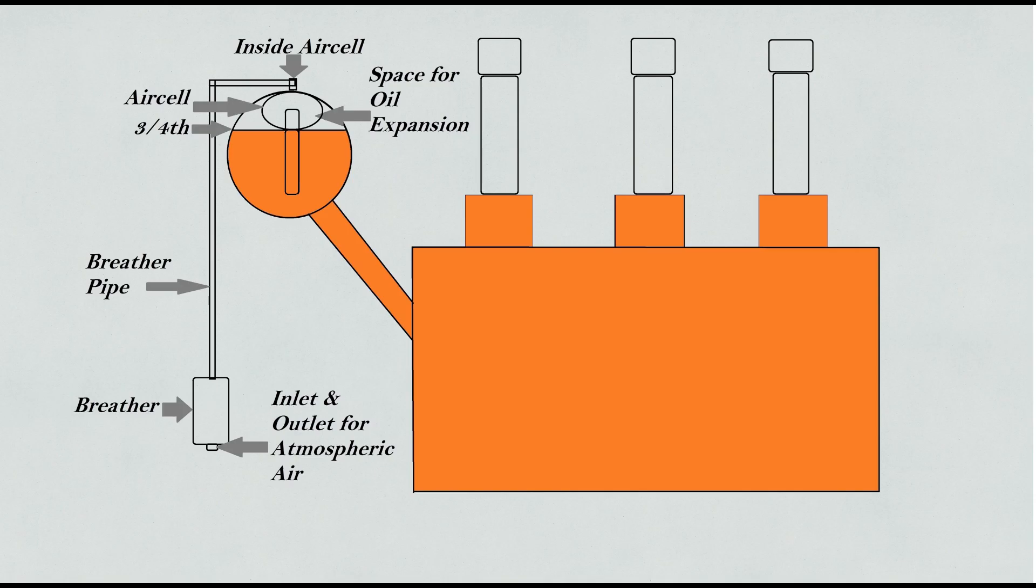Hence, when transformer oil temperature drops, oil contracts, and the oil level in the conservator goes down. So to compensate this contracted volume of oil, atmospheric air gets inside the air cell through the breather, and the air cell expands, compensating for the contracted oil volume.